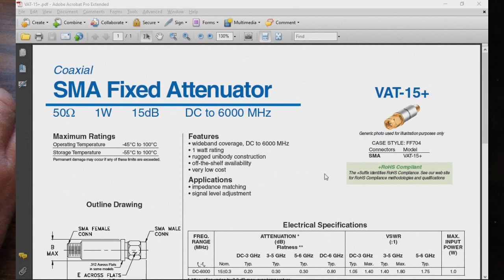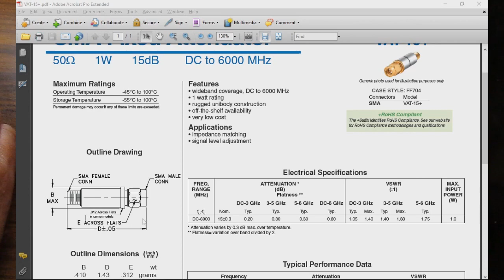And this is looking at the data sheet for Mini-Circuits for the VAT-15+. You can see they've specified the frequency range from DC to 6 gigahertz. The nominal attenuation is 15 plus or minus 0.3 dB. For DC to 3 gigahertz, it's typically plus or minus 0.2 dB, and then 3 to 6 gigahertz, it's typically 0.3 dB. So if we talk about 15 dB plus or minus 0.3 dB, you can see it looks quite a bit worse than what the manufacturer claims.